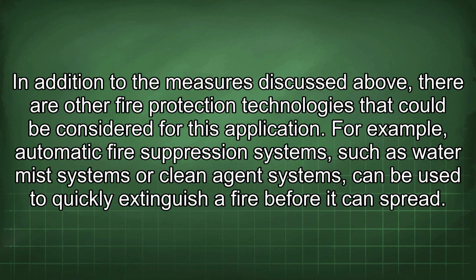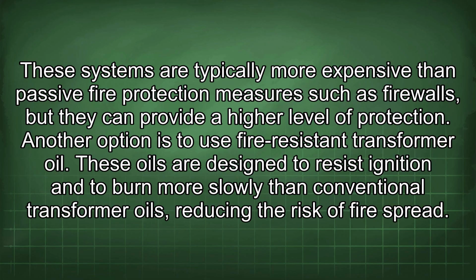In addition to the measures discussed above, there are other fire protection technologies that could be considered for this application. For example, automatic fire suppression systems such as water mist systems or clean agent systems can be used to quickly extinguish a fire before it can spread. These systems are typically more expensive than passive fire protection measures such as firewalls, but they can provide a higher level of protection. Another option is to use fire-resistant transformer oil.